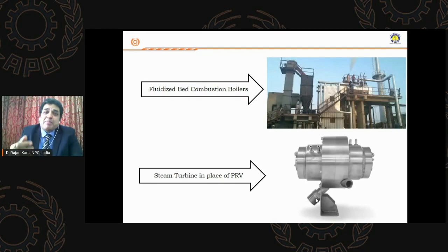So what you do, you keep a PRV. So what is PRV? PRV is a pressure reducing valve. A simple PRV will reduce your pressure, but the steam will be in the superheated condition, and you won't require that superheat. Right. So what you can do is, nowadays all these PRVs are coming with a desuperheating station. You generate some additional amount of steam at the end, because they will be adding some amount of water when the PRV is added, the superheating part will come down, and you get more steam with the same amount of coal. So this is one pretty good advantage.